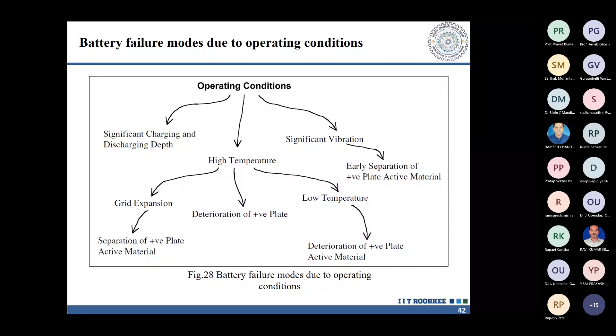This is because of the early separation of the positive plate and the active materials. High temperatures are also a problem, and low temperature too. It can deteriorate the positive plate, whereas at high temperature grid expansion takes place, and also separation of the active material from the positive plate will occur, in case of lithium. These are things we require to check, and based on that we may require a heating or cooling system in our battery management system.